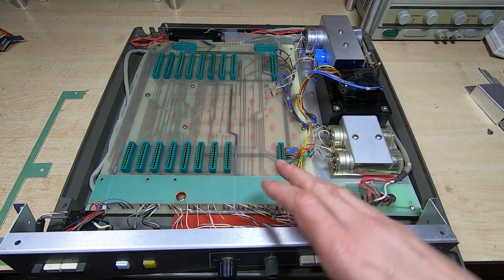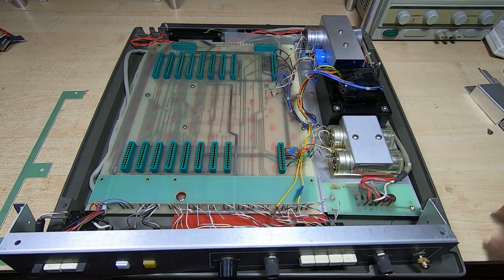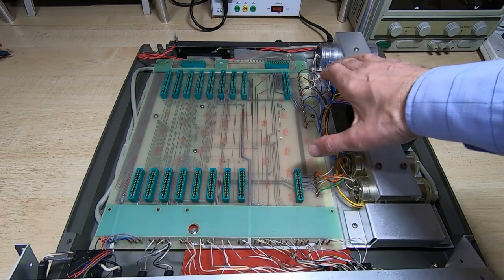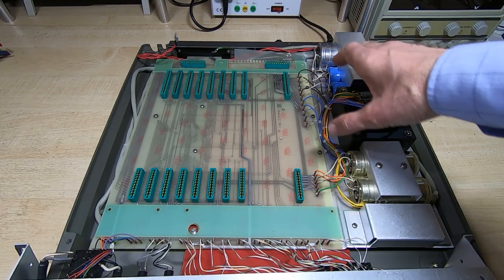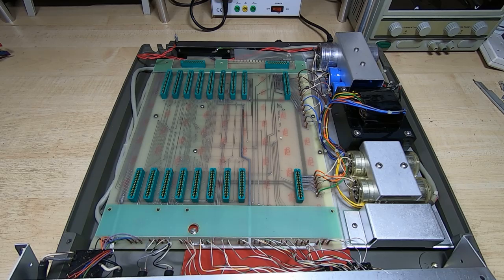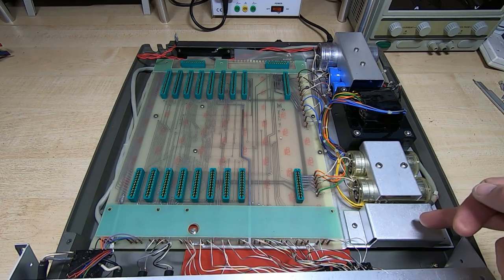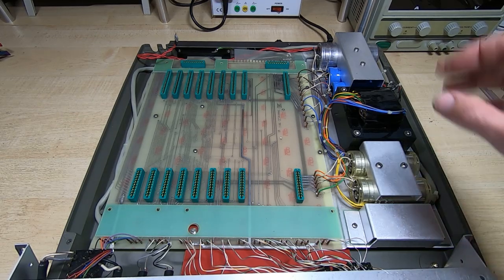We'll get these reconnected, and then we can refit the control panel and the electronics cage. So I've got all the wires reconnected, double checked them to make sure they're in the right place, cleaned up the insulation pads and dropped those into position, and put the cover on the high voltage generator.